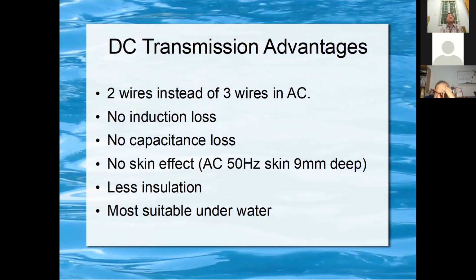And the other one called skin effect. When you pass electric current through the wire, let's say at 50 hertz, which is our AC supply, if your wire is very thick, thicker than let's say radius 9 mm, so diameter is 18 mm. Let's say your cable is very thick, 10 cm, but you pass AC through a thick cable, only the outside 9 mm is conducting current. The center part has almost no current. This is called skin effect.